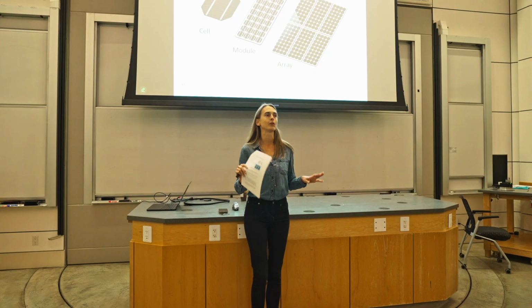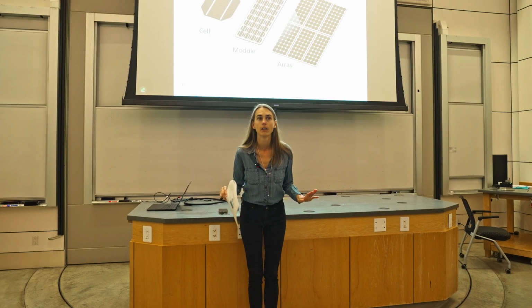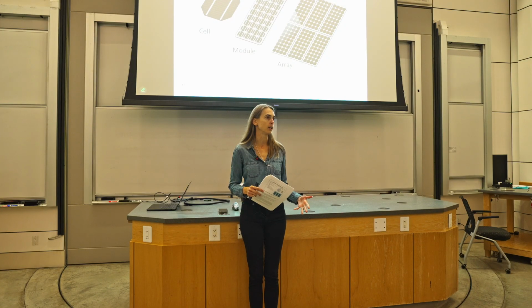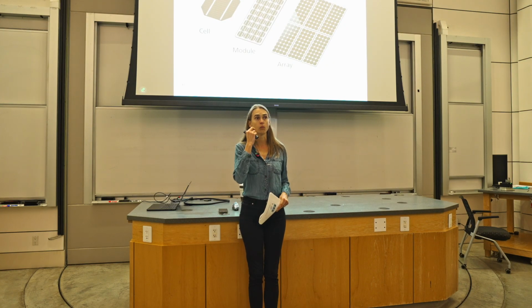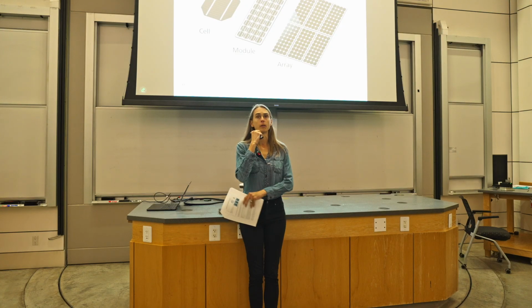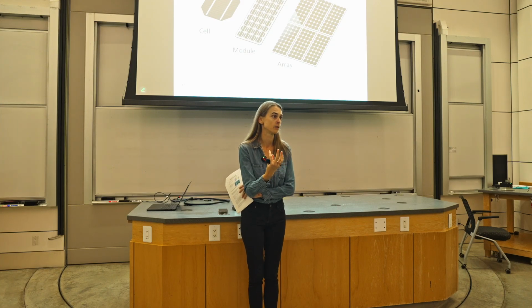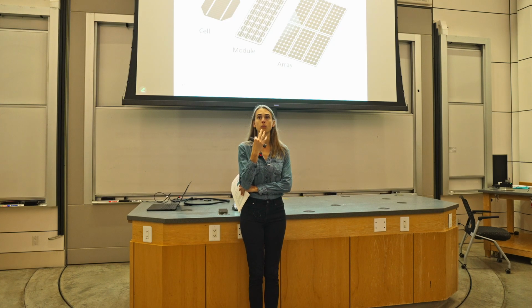I can't tell you guys enough how many stories I've heard from the field of a solar project that's been sited on somebody's rooftop or carport that gets shaded. A portion of it gets shaded at some point during the year because the solar installer or solar contractor didn't do some sort of shading analysis when they were installing the project. And they don't necessarily have an incentive to do that, right? Because they're just installing the project. They're not the ones actually benefiting from the production.